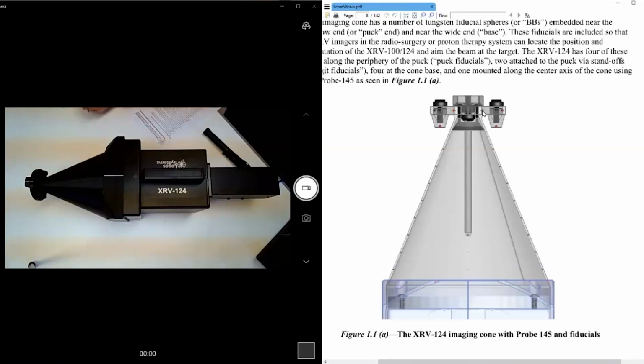2 other holes in the puck support the base of the probe 145. The probe has a thin carbon fiber reinforced plastic rod that suspends a BB directly under reference hole F, approximately 145.3 mm away from the origin at z equals 145.3. This BB is close to the center of the imaging cone where x equals 0 and y equals 0. Diagnostic deliveries usually aim for x equals 0 and y equals 0 at some chosen distance from the origin.